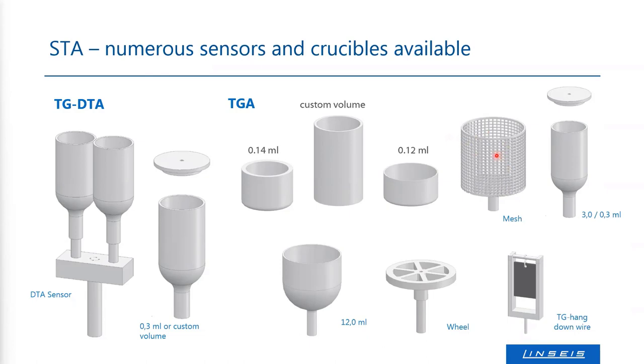The mesh-type sample holder is used if you want to observe reactions of your samples with the reaction gas. Wheel-type sample holders can be used for larger samples. We also have hang-down sample holders used for oxidation or reduction processes of metals, for example, which can be monitored.